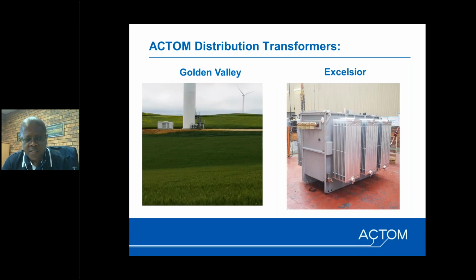The picture on the left is a Golden Valley site. It's a wind farm. The transformer is housed in a packaged transformer kiosk. That's a PTK. It's manufactured in collaboration with our switchgear division. It consists of a ring main unit, the transformer, and an LV panel. But with the new requirements for skid solutions, we would look at something similar to that, although the recent requirements are that the transformer must also be exposed and not enclosed. The picture on the right just shows the transformer standing in our test facility undergoing test, and that was to be supplied to Excelsior Wind Farm.